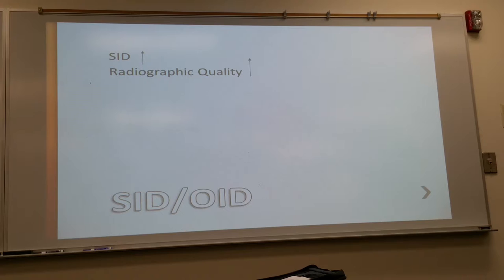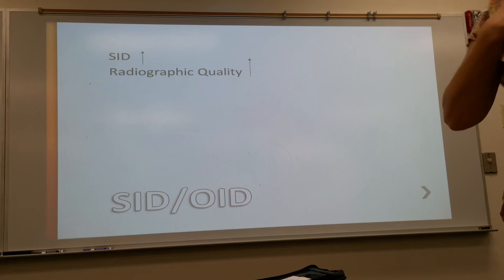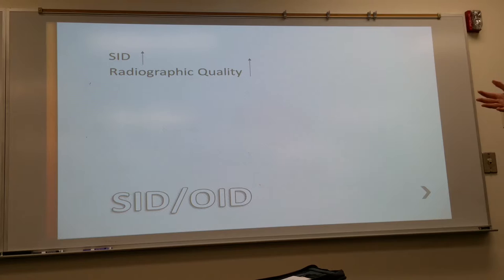And so we want to get as much distance as we can reasonably. We're not going to back up 10 feet because what happens as you increase your distance? What do you have to do to your exposure factors? Bump it up. Increase it. Direct square law. So there's a compromise there. You want an increased distance and get the heart to true size, but then you don't want so much distance that you're going to have to give the patient more radiation. So that's why we do chest x-rays at 72 inches.